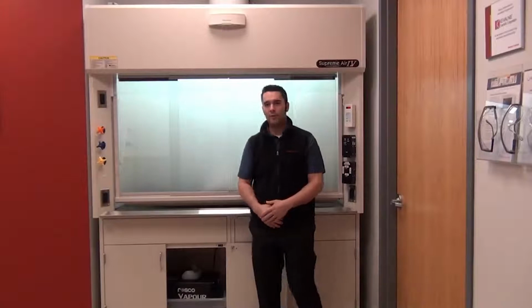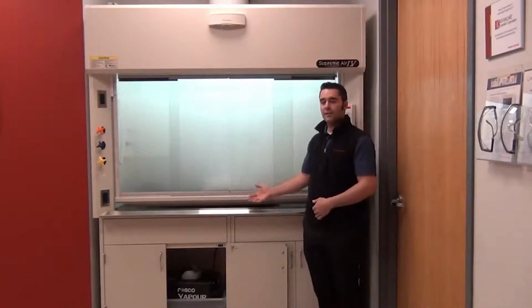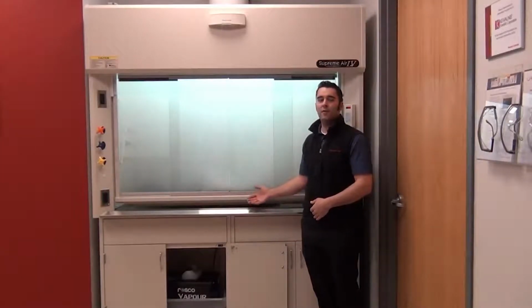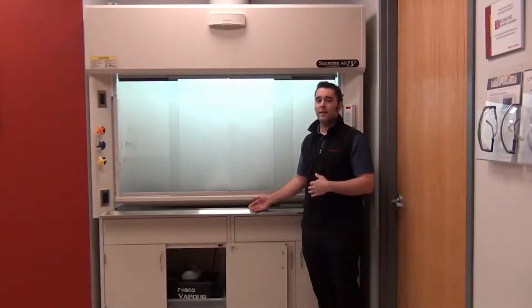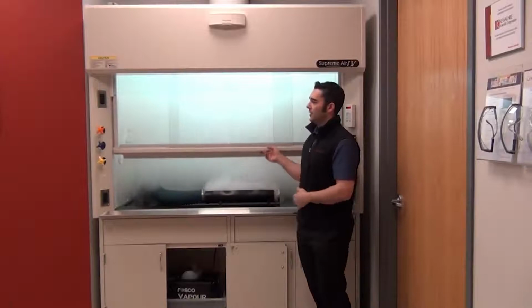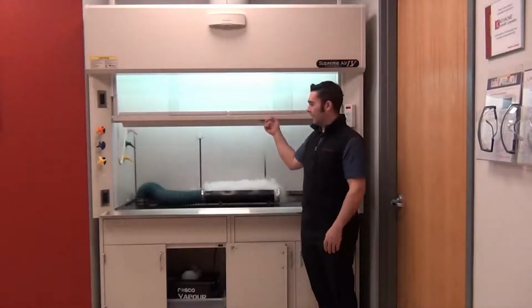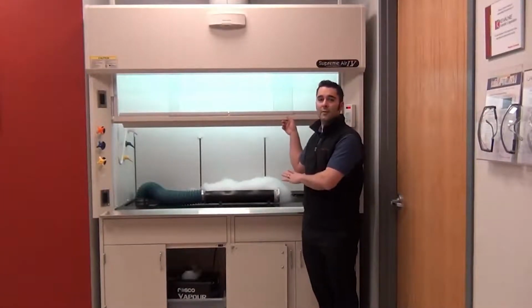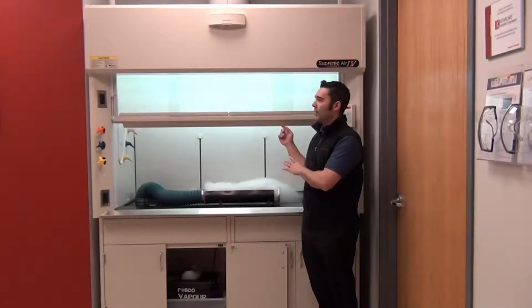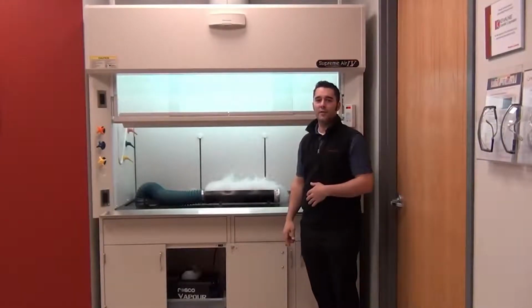Secondary to safety of fume hoods is energy savings. Everybody realizes that fume hoods use the most amount of energy when it comes to any airflow control device inside of a chemistry lab. When you're using a single fume hood like this fume hood, when left running at 100% flow, it could use as much energy as 5 small houses in the United States. So if I'm leaving this sash open like this, again, I'm guaranteeing that I'm containing my chemicals inside of my fume hood, but I'm wasting a lot of energy when this fume hood is left open.